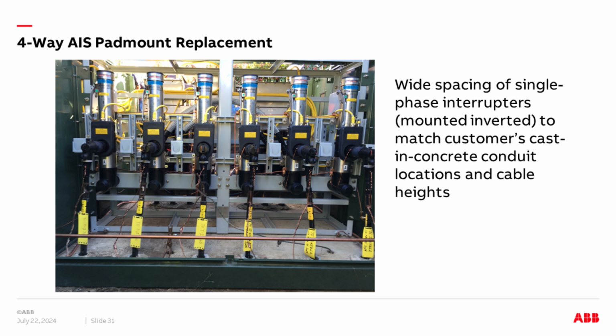Then I'll interject a question here real quick from the audience. Big utility out west: is there a gauge, or do you have alarms for your vacuum switchgear when the vacuum has been compromised? No, there's no vacuum monitoring in this gear. We don't have a history of problems in this space where that would appear to be needed. Long life has been proven out so far, so that hasn't been an issue. Good, thank you.